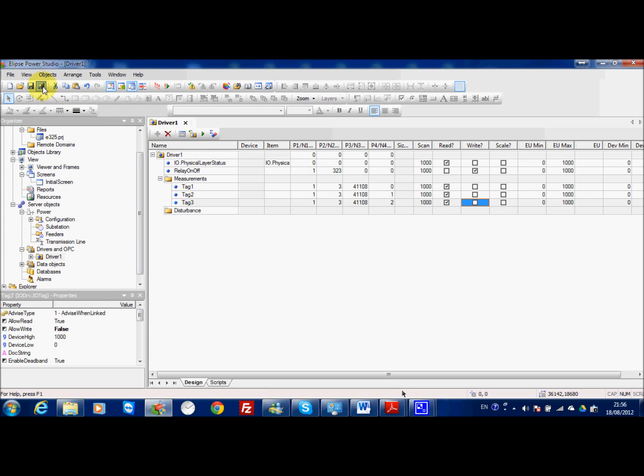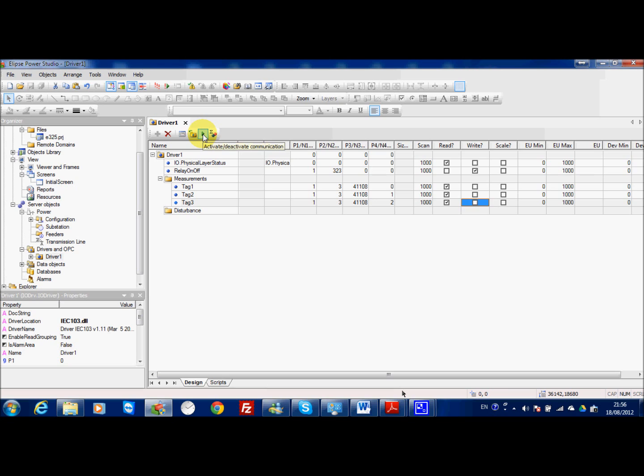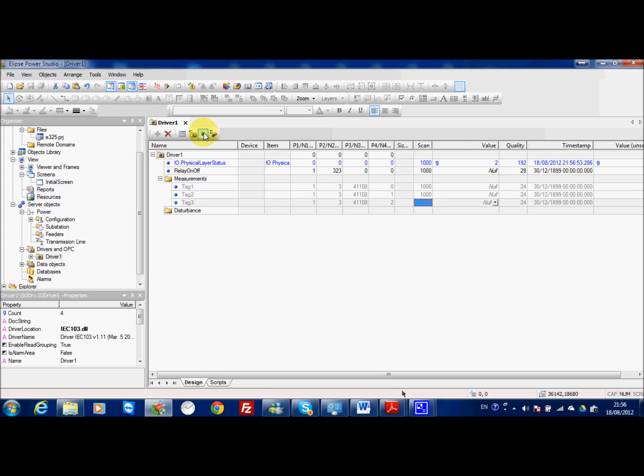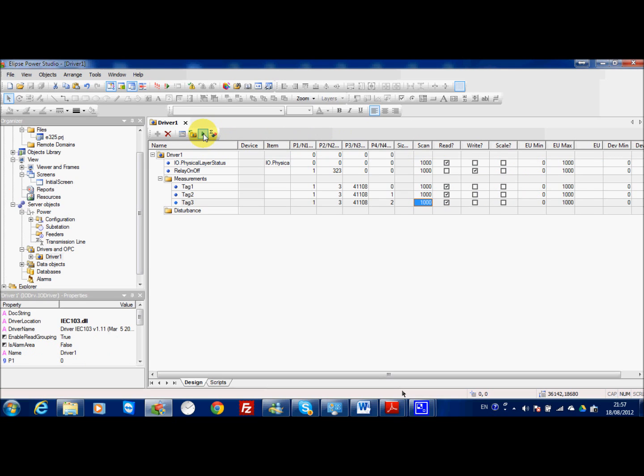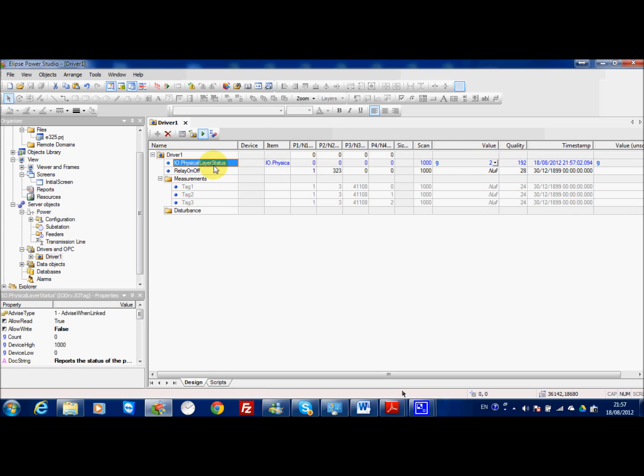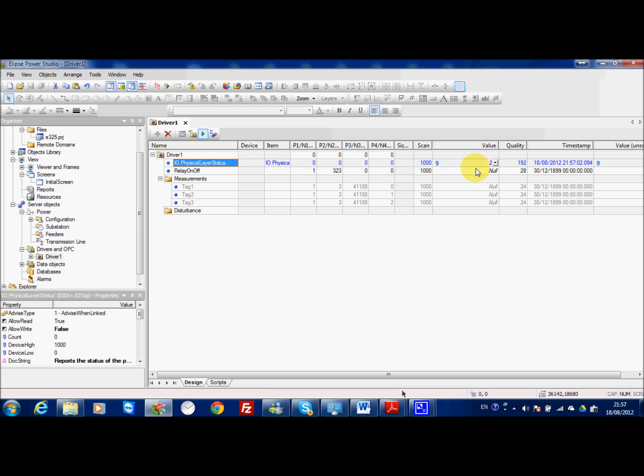I can start the communication by this way by activating my driver. So here the value changed to 2. It means that the cable is connected. If I start again it starts from 1 to 2, which means the cable connection is okay. This tag is common to every protocol so it has nothing to do with IEC-103 but you can test the communication, just the cable communication, the physical layer by this way.